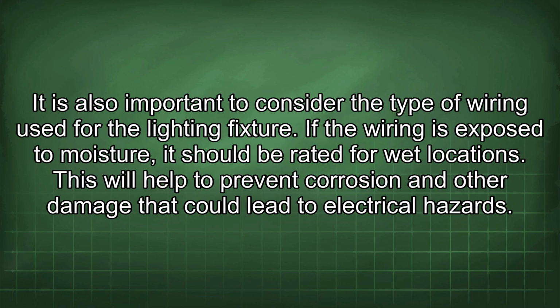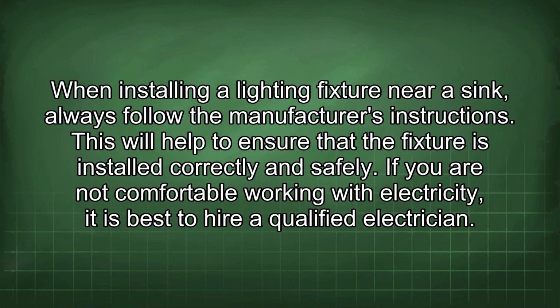It is also important to consider the type of wiring you use for the lighting fixture. If the wiring is exposed to moisture, it should be rated for wet locations. This will help to prevent corrosion and other damage that could lead to electrical hazards. When installing a lighting fixture near a sink, always follow the manufacturer's instructions. This will help to ensure that the fixture is installed correctly and safely.